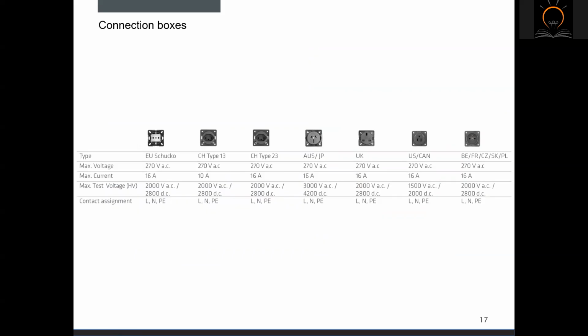Depending on the installed test socket, different limitation can arise. From the table, it can be seen that different test sockets can withstand different test voltages. For example, type 13 can only withstand test voltage up to 2000 volts AC, whereas Australian test socket can withstand test voltages up to 3000 volts. And unfortunately, the US test socket can only withstand test voltages up to 1.5 kV AC.